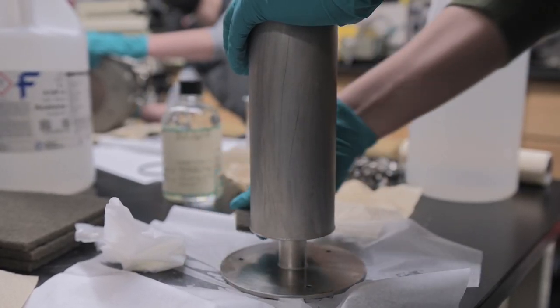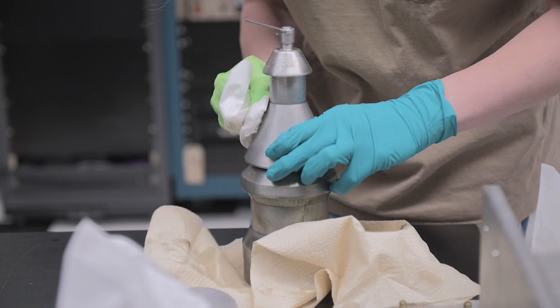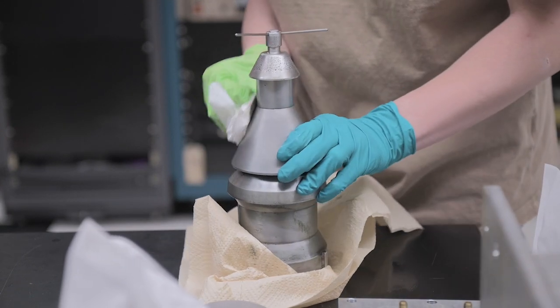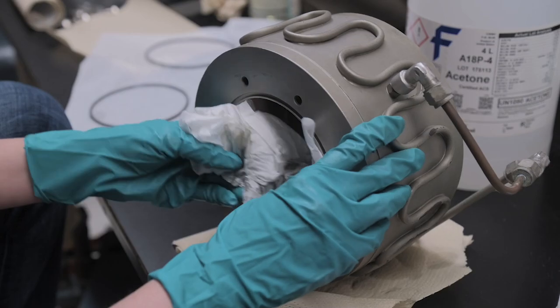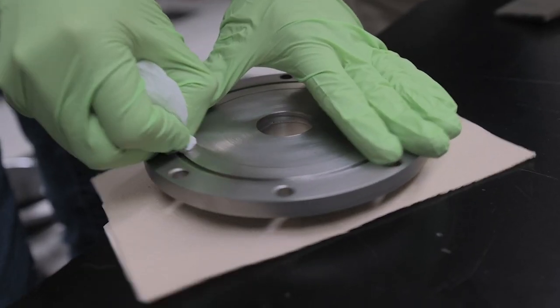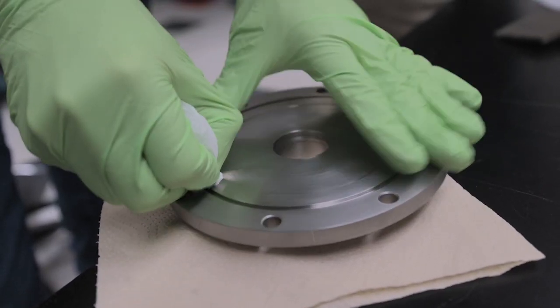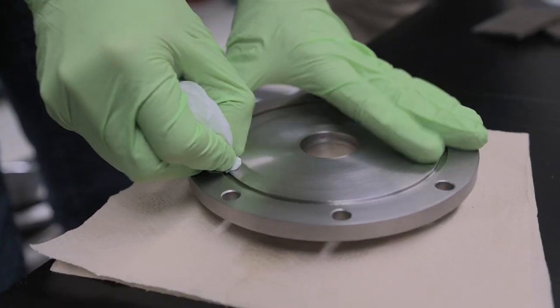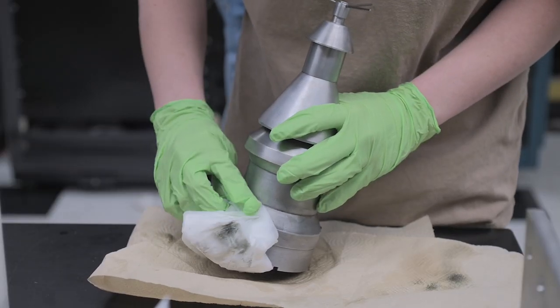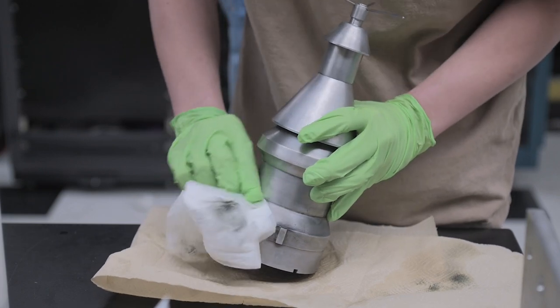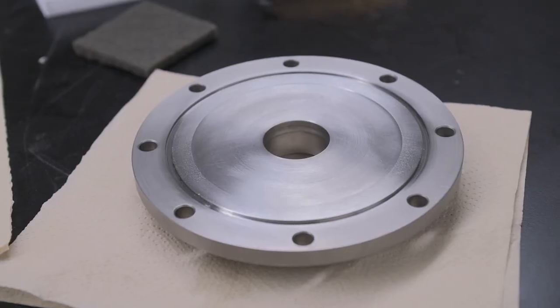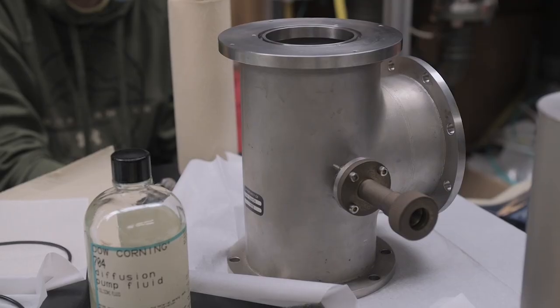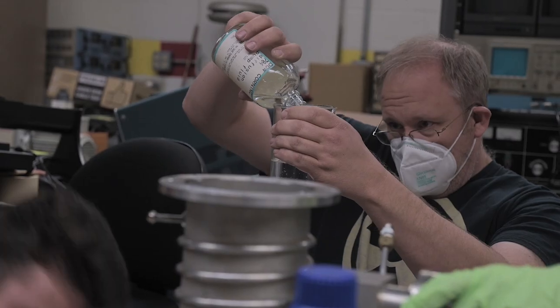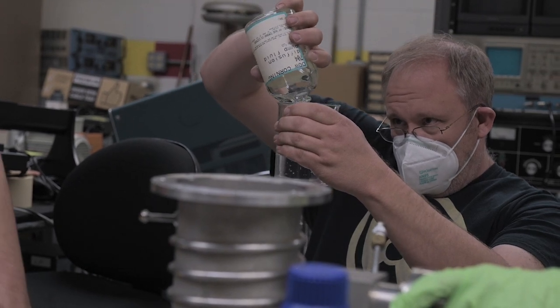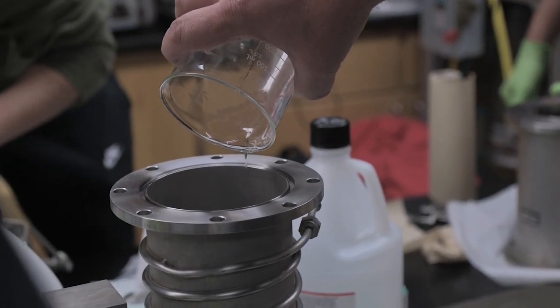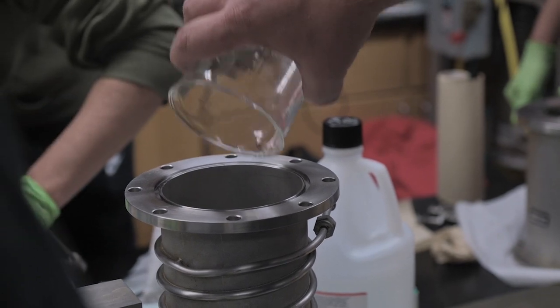A Scotch-Brite pad is then used to clean any surface to which carbonized diffusion pump oil could be clinging. One final wipe over with Kim wipes and acetone prevents any particulates left from the scouring process from interrupting any of the new O-ring seals. And with that, all of the pieces of the diffusion pump are shiny and clean, ready to be reassembled with brand new diffusion pump oil. The diffusion pump oil of choice is Dow Corning 704.